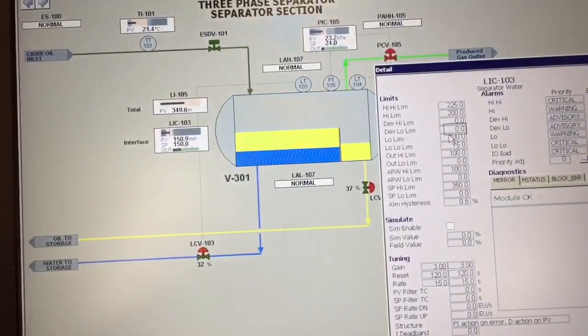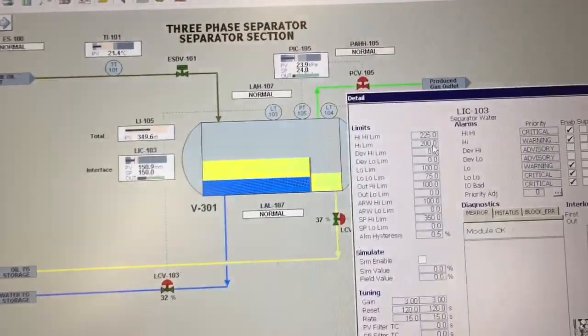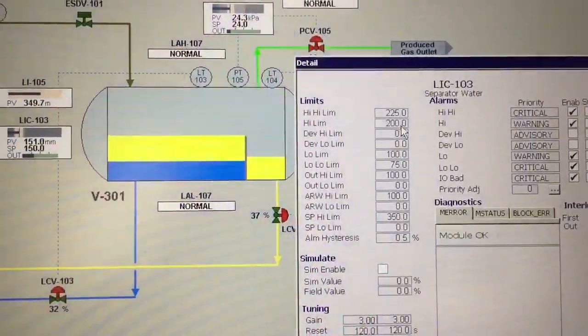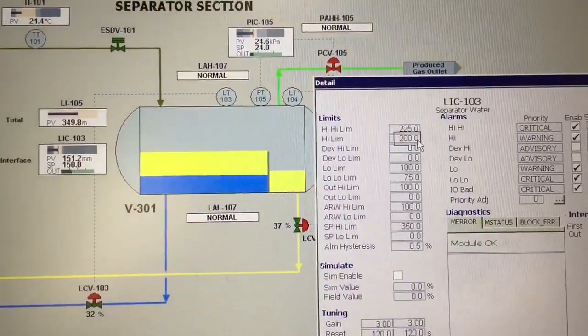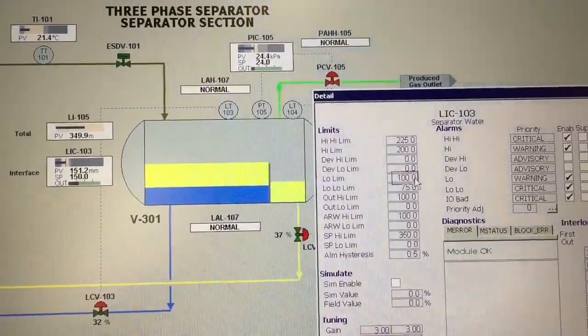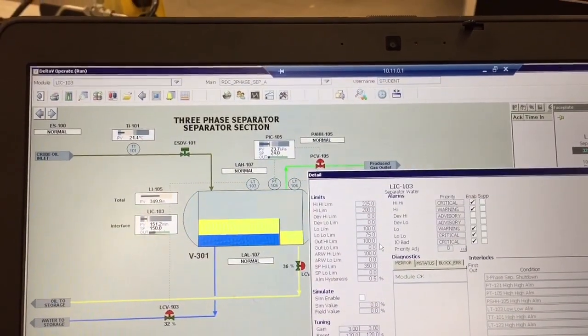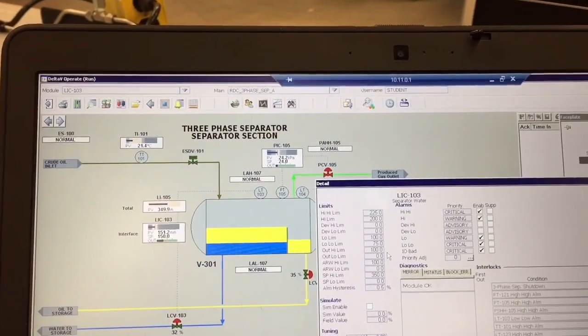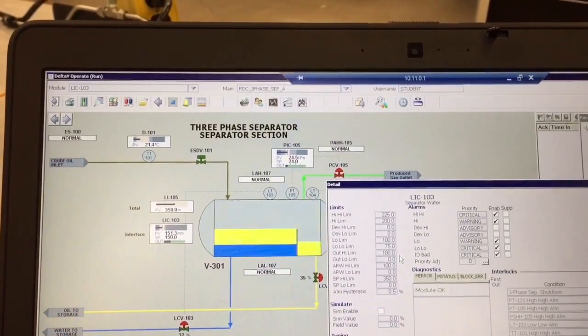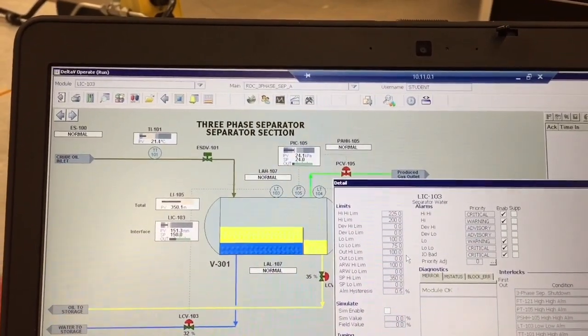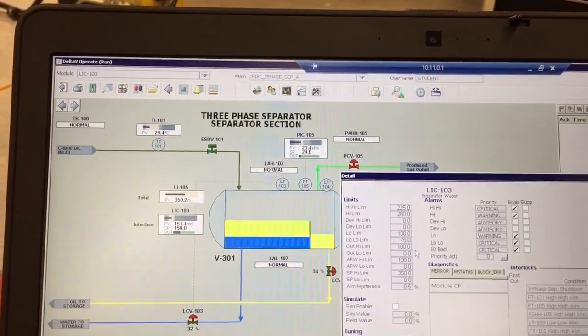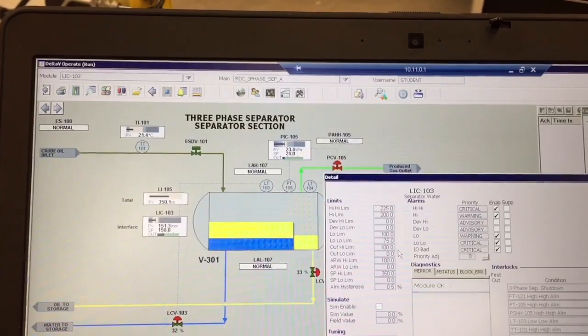Also notice here our high alarm. Our first high alarm rings in at 200 and our low rings in at 100. So we only have 100 millimeters to play here, about 4 inches of room. If we go outside those limits, if we go too high, our interface probe can't measure the interface. There needs to be a minimum of 4 inches on top of the water for it to measure properly.